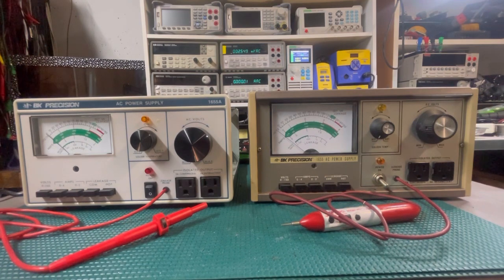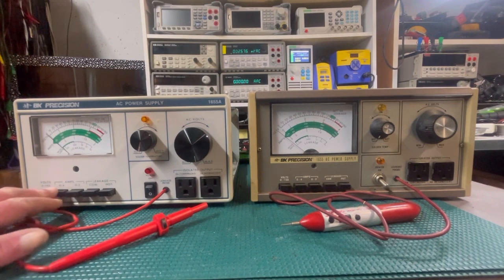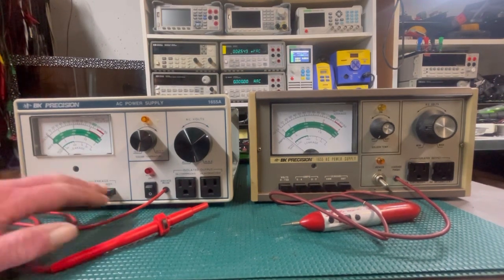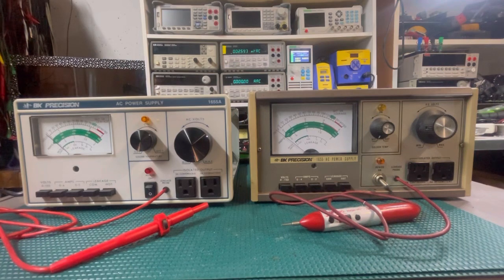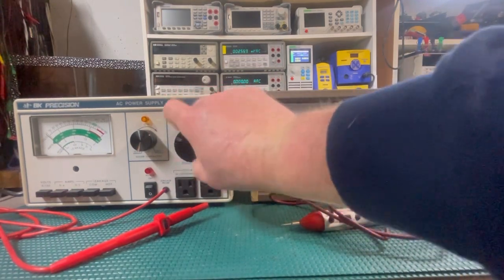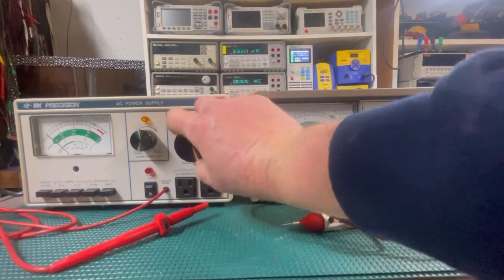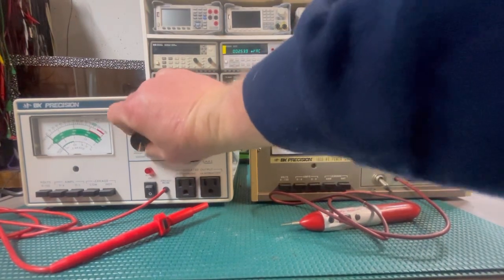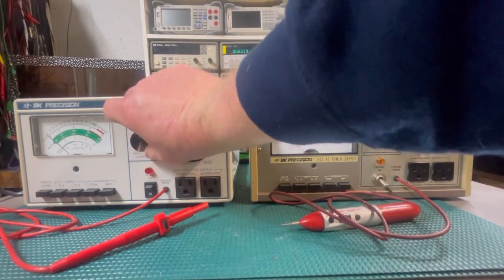So basically, I showed you guys the buttons and what those do, how they change the gauge, and you do your leakage current test, or measure your amperage going out of the isolation. And then this one is obviously we adjust our voltage from 0 to apparently 160 volts, even though the gauge only goes up to 150. And then this one right here, we're not plugged in because I still got the top off, but there's a receptacle on the back that I'll show you. The receptacle's independent of these.